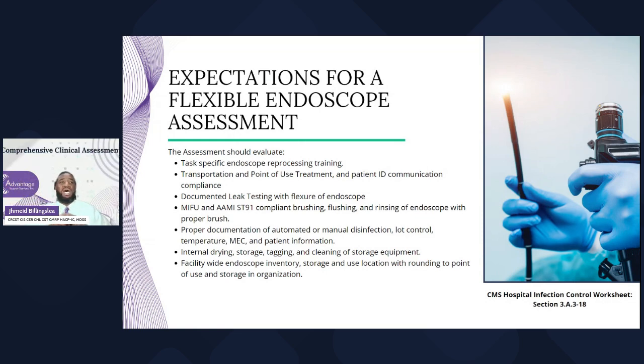Internal drying, storing, tagging, and cleaning of storage equipment. And again, that flush that's on an automatic, the AER is not a drying cycle. ST91 makes that clear. And do you have an inventory of all the endoscopes? Because you can be doing it perfect in the area where you reprocess endoscope. But then you find out this clinic has an endoscope that they don't send to you. This place has it. So having a facility-wide inventory also gives you the opportunity to make sure that everybody is compliant.